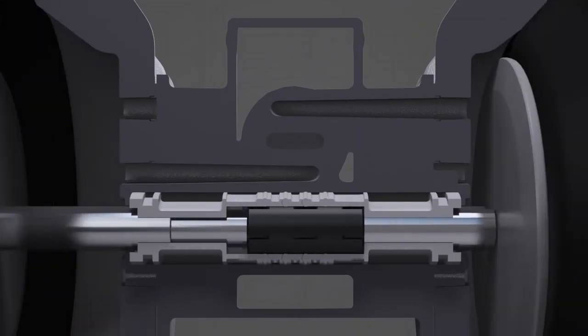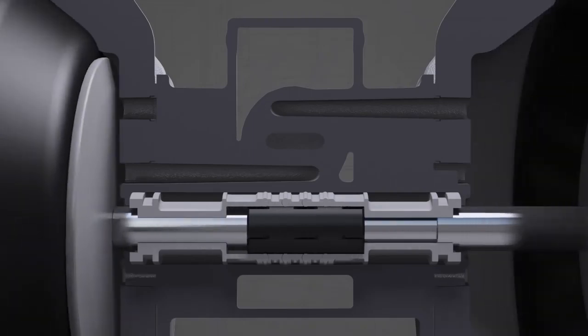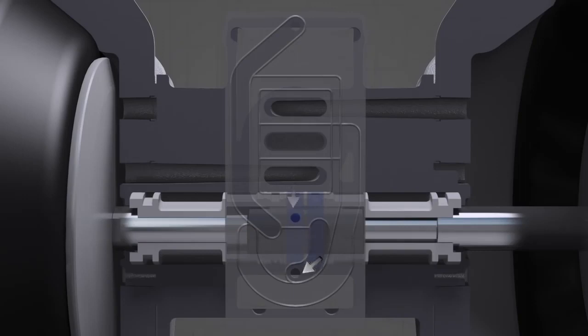The pilot air valve has two logical states, which we will call left and right. Pressurized air enters chamber three in the middle of the pilot valve sleeve. Chamber three is always under pressure. When the pilot air valve travels far enough to the right, chambers three and four are connected. This allows the pressurized air from chamber three to pass through and exit chamber four, which moves the main air valve upward.